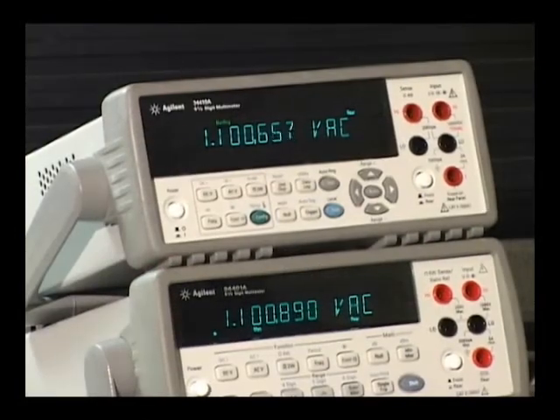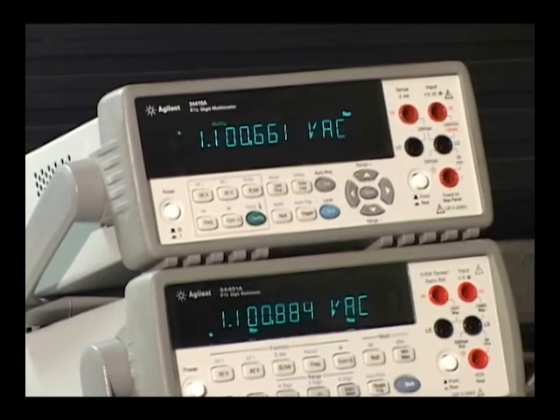The 34410A uses a digital sampling technique to give incredibly fast AC measurements, peak-to-peak measurements at 50,000 readings per second. And in DC volts, you can take 10,000 readings a second at five and a half digits. This is almost a 300X improvement over the 34401A.